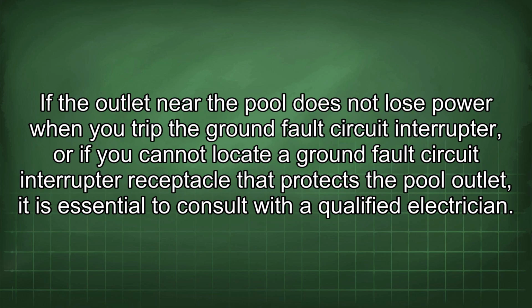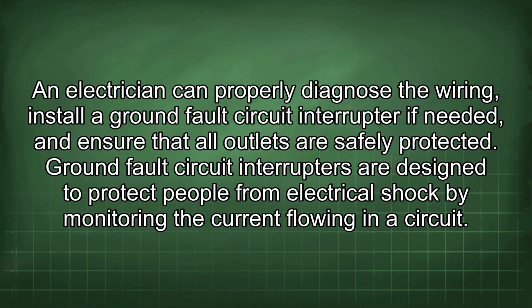If the outlet near the pool does not lose power when you trip the ground fault circuit interrupter, or if you cannot locate a ground fault circuit interrupter receptacle that protects the pool outlet, it is essential to consult with a qualified electrician. An electrician can properly diagnose the wiring, install a ground fault circuit interrupter if needed, and ensure that all outlets are safely protected.